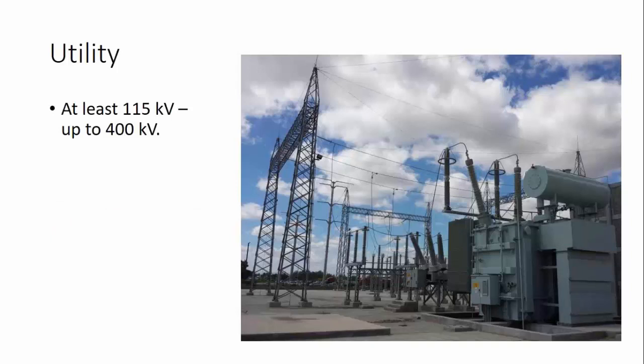Let's continue. Now, a typical electrical system for an arc furnace is formed by a very robust utility. In Mexico, we have at least 115 kilovolts up to 400 kilovolts. I don't know about any other parts of the world, but these are Mexican voltages. They are very high voltages and they imply a very robust system, a very stable line. It's dedicated to the steel mill.